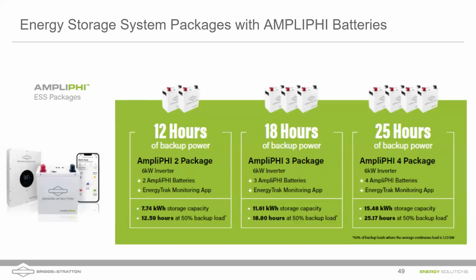The point is that about half of that energy would be used during an outage - half the power normally used. So you'd get a number of backup hours based on using half the energy you normally do. We've taken the capacity of these batteries and divided the kilowatt hours by about half a kilowatt, meaning about 500 watts. That gives you 12 hours of backup with 2 AmpliPHI batteries, 18 hours with 3, and a little over a full day with 4 of those batteries.